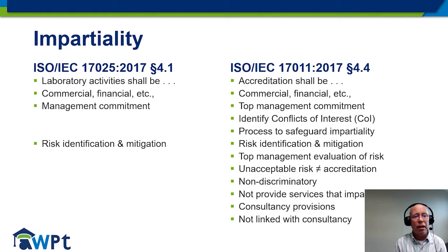Now, 17025, if we take a look back at impartiality, it says that the laboratory shall be an organization that acts impartially, that it manages and addresses commercial and financial strains, so that these undue pressures do not cause people to make decisions that would affect the consistency and maybe even the competency of the staff that's making measurements in your conformity assessment body, or inspections, or certification claims. Okay, and it also requires a management's commitment to that, and typically that will show up in a quality policy or something like that, that you're demonstrating commitment.